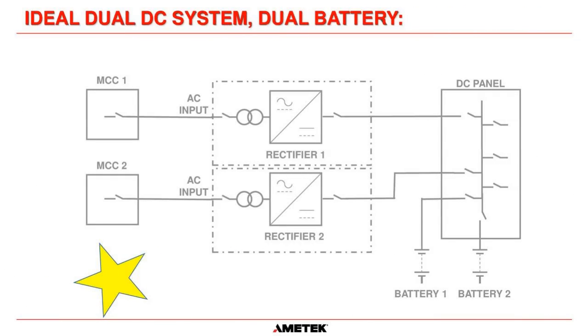Okay, we have exactly the same dual redundancy on the rectifiers, the chargers, but now we have battery 1 and we have battery 2, each protected by their own DC disconnect. And that means if battery 1 fails, we can go in and open its DC input, DC breaker, and we can leave battery 2 supplying the load circuits if necessary, or being charged from both chargers. And we can go in, we can replace this battery, we can do maintenance on it without jeopardizing the load circuits whatsoever.